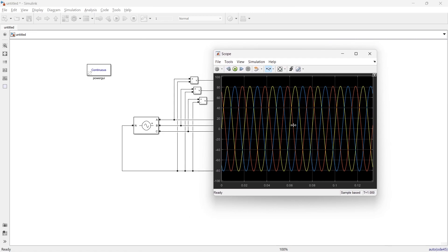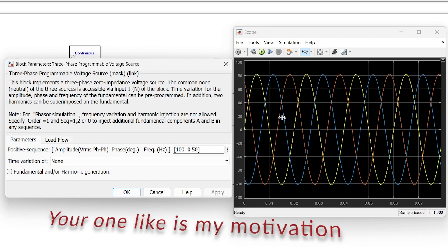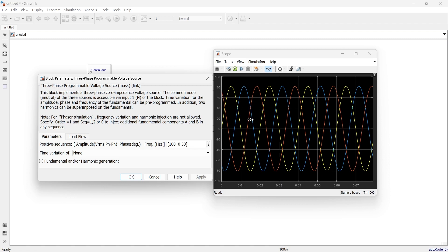We gave an amplitude of 100 V RMS phase-to-phase, but in the scope the peak is around 80 V, which is less. This is because that quantity is phase-to-phase, or line voltage — the line voltage is 100 V. What we are measuring here is the phase voltage, which is less than the line voltage by a factor of root three. If you want to observe the line voltage, let me show you.